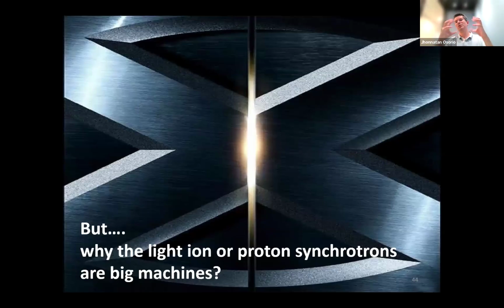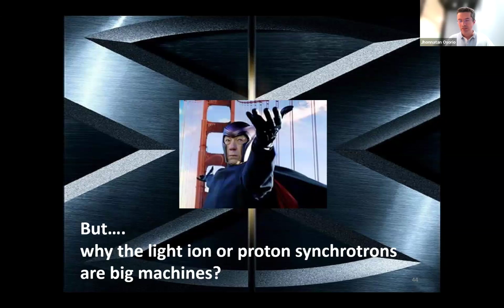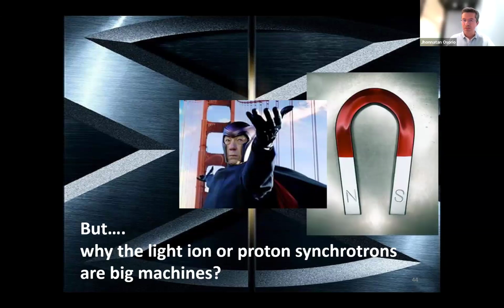I want to show you how the beam behaves inside the cyclotron and how difficult it is to control, since the beam has a certain emittance, basically the size of the beam inside the cyclotron. And this is basically the charm of this kind of machine: you need to tune carefully all the magnets, all the RF cavities, all the diagnostic elements in order not to lose your beam and to deliver the beam all the way to the patient. And maybe one of the basic questions is why these machines are so big. And basically, the answer to that is the magnetic field.